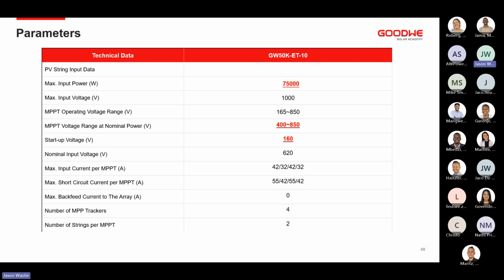We look at the PV string input data, so it's unique. It does allow for higher PV oversizing with the ET50, 1.5 times that of the inverter's capacity. So we allow for your standard 50 kVA AC output with the additional 25 kilowatts from PV, then you'll be able to charge your batteries directly.